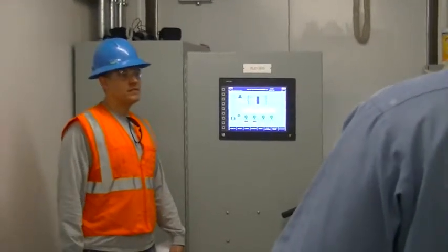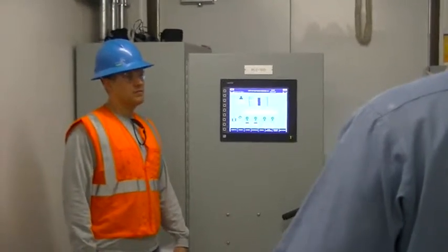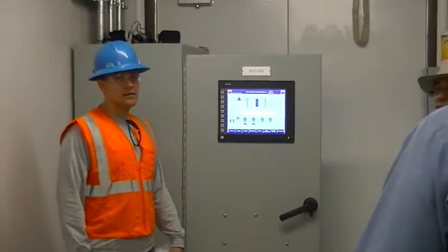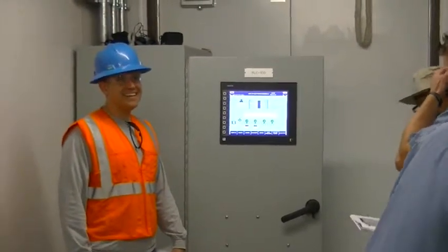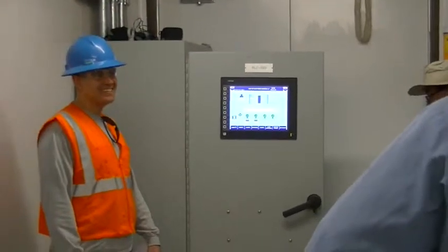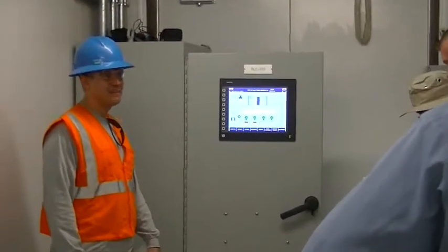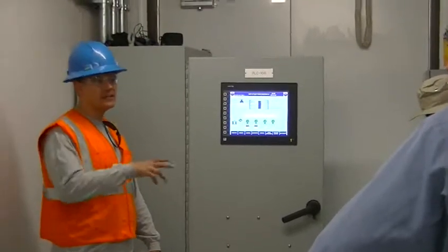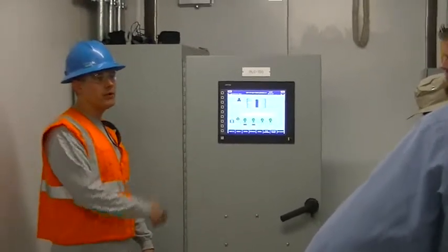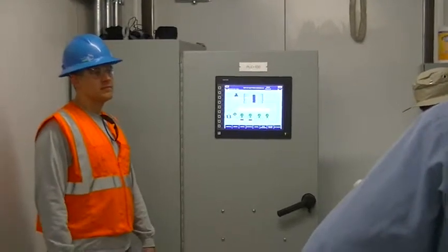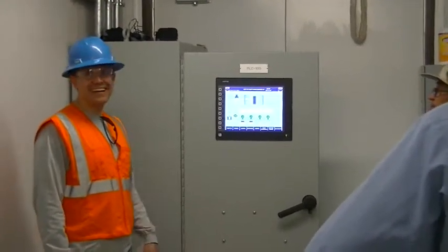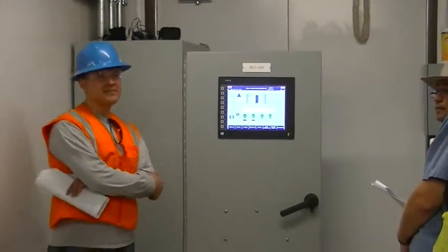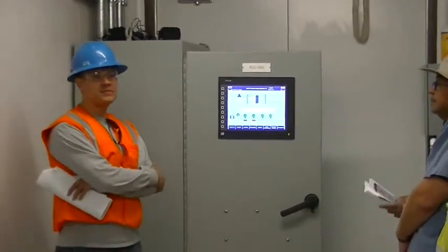How much pressure are you talking about when those kick on? Is it over 70 pounds? Like a bunch of call-ups, Bob. I don't know, we haven't turned them on and connected to the system yet. We've done it open pipe, so it flows a lot of water, and even then it still surges pretty good. You're gonna have several hydrants open in order to kick those suckers on.